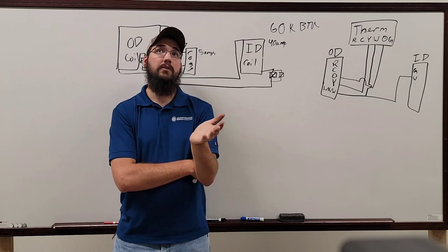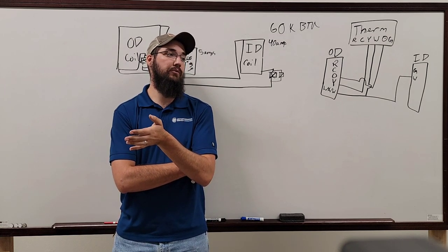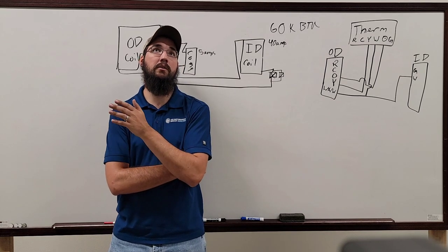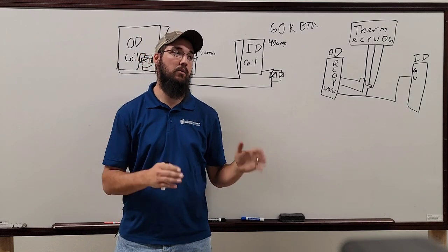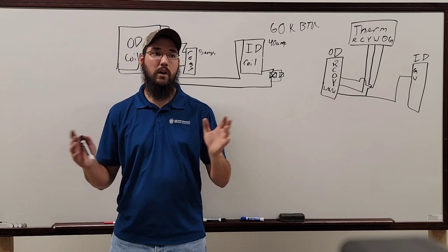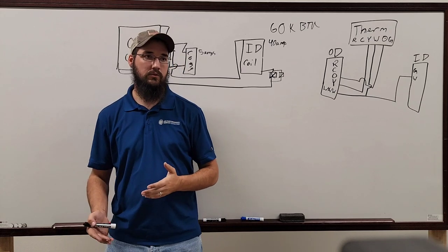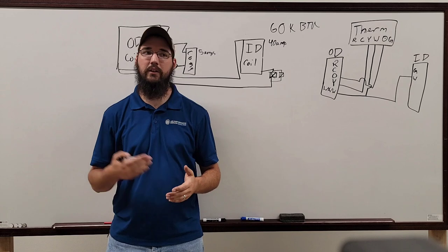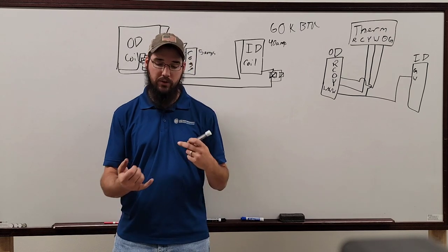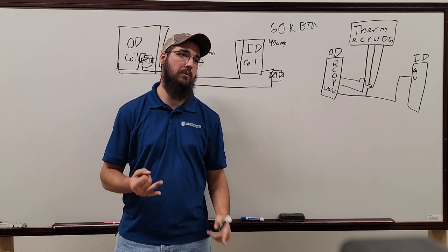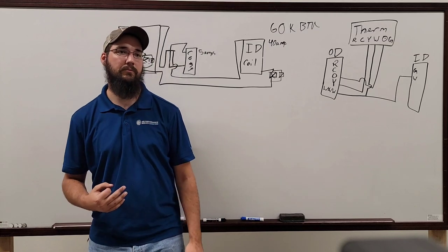Well, and honestly, the most common failure point I've ever seen with a heat pump system is the defrost control board. I've rarely seen, even on the cooling side, a specific component on a board fail more than defrost controls. I don't know why. You change them all winter long. They constantly fail for whatever reasons. Doesn't matter what manufacturer you're working with. Whether it be the fan relay fails, they don't sense the sensors properly, you know, just go down the list. They constantly have issues. Very common weak point.